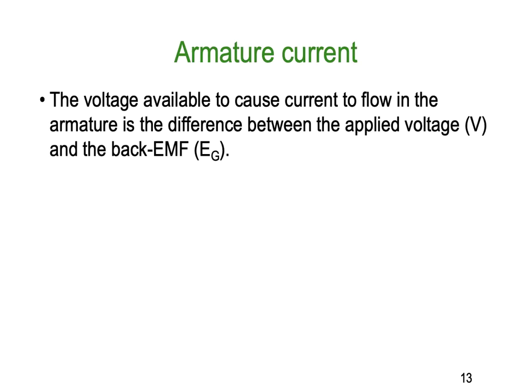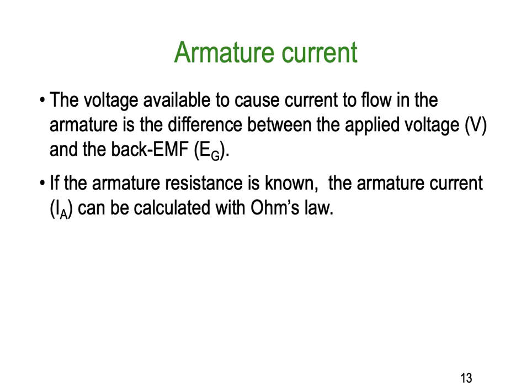Regarding armature current: the voltage that causes current to flow in the armature is the difference between the applied voltage V and the back EMF E_G. If the armature resistance is known, the armature current I_A can be calculated using Ohm's law: I_A = (V − E_G) / R_A. This is simply DC Ohm's law giving us the voltage inside the armature subtracted from the applied voltage.